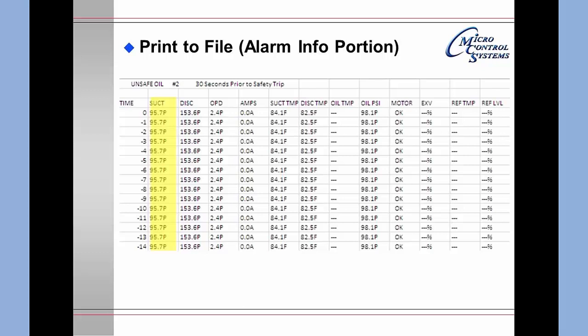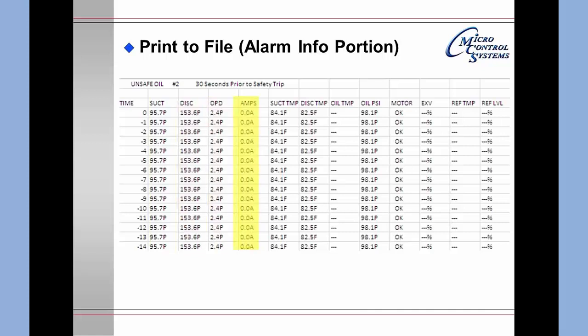The suction pressure never changed. The discharge pressure never changed. The oil differential never changed. And there were no amps ever drawn. So while we fired our relay there was obviously no control power because we never saw the compressor start.